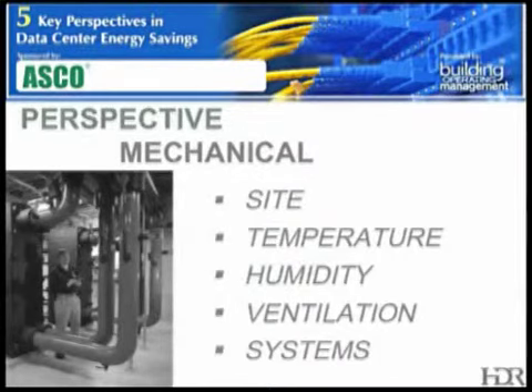I think the main point I wanted to make on humidity was the fact that if you're going to choose an operational humidity and let it really rise up to one of the allowable zones, you have to be sure that your chill water temperature has been coordinated with that. In other words, we want the chill water temperature to be raised to be above the dew point if at all possible. Otherwise, that chill water is not just removing heat, but we're spending a lot of energy removing the moisture. It's taking out humidity and consuming chill water capacity and energy to do that. So I think you've got to be careful that you've looked at the psychrometrics and that your chill water applications are properly aligned with that.